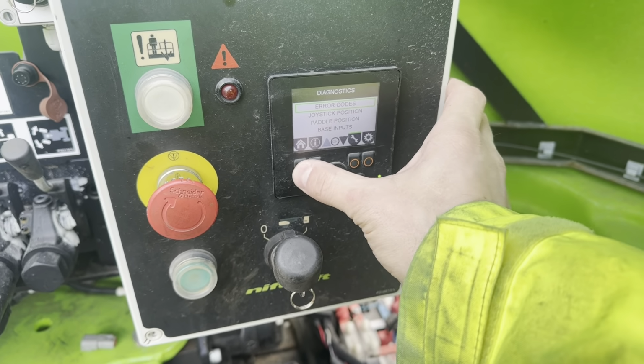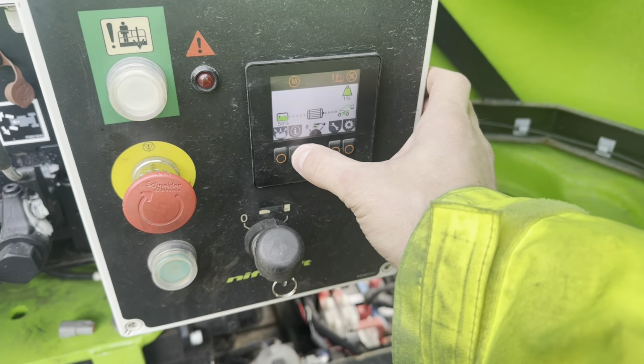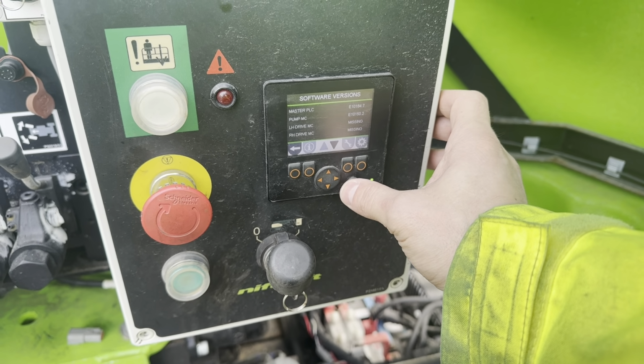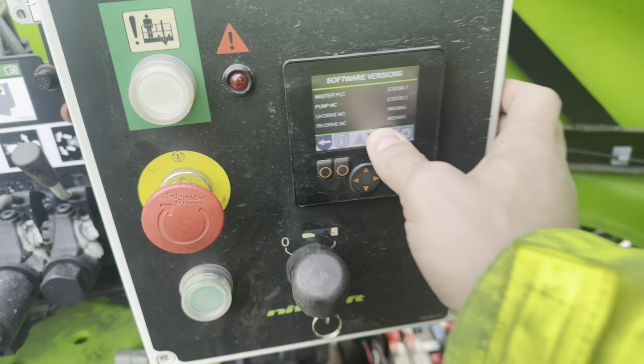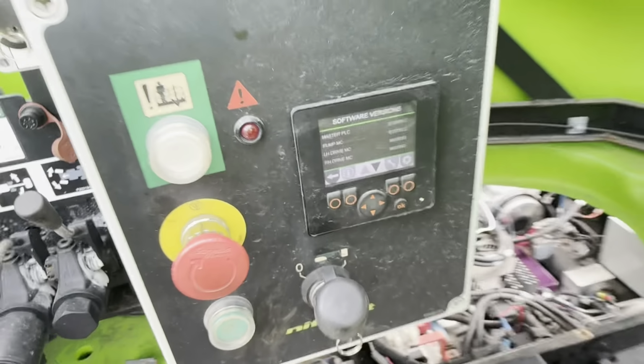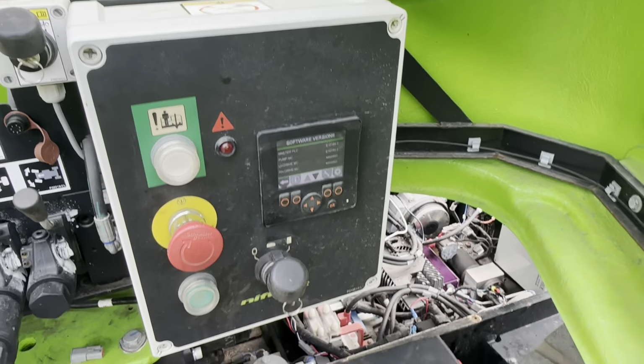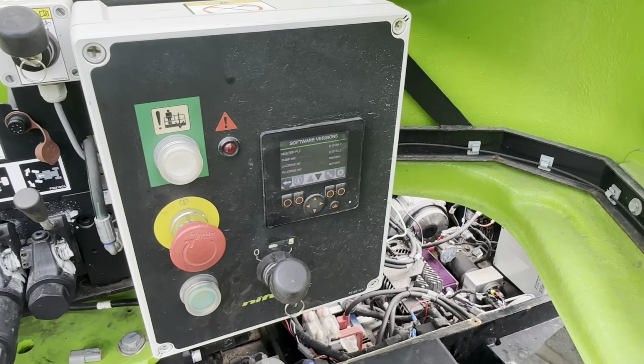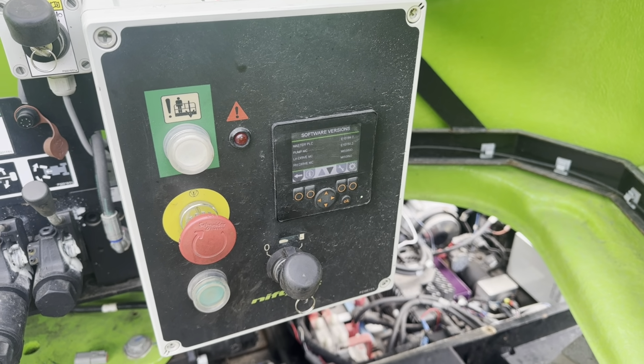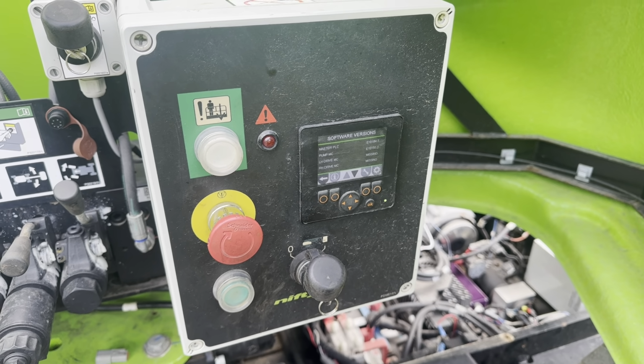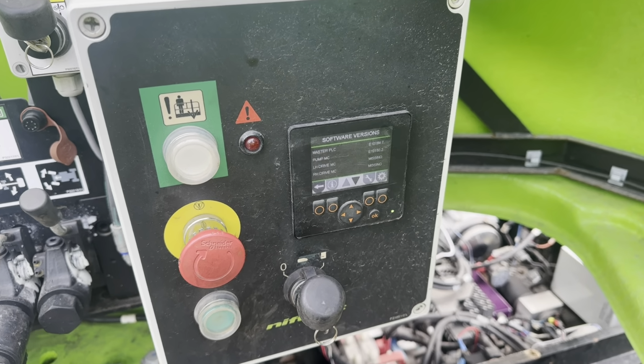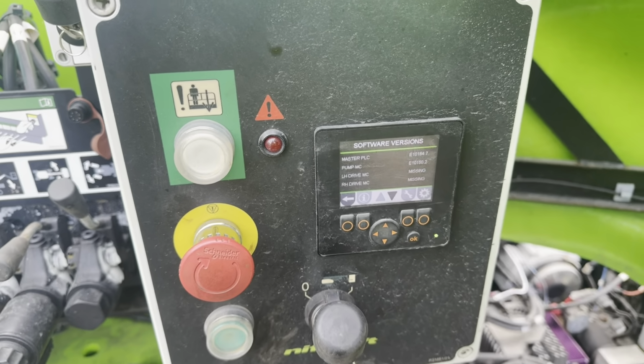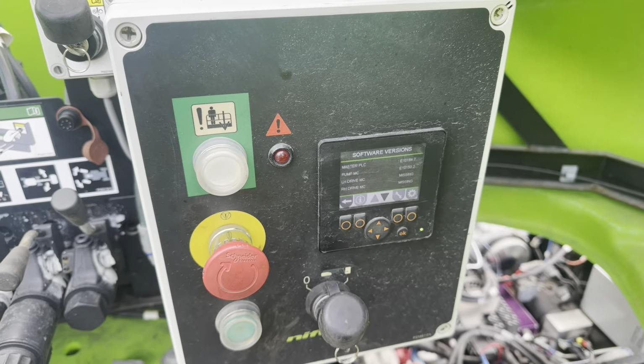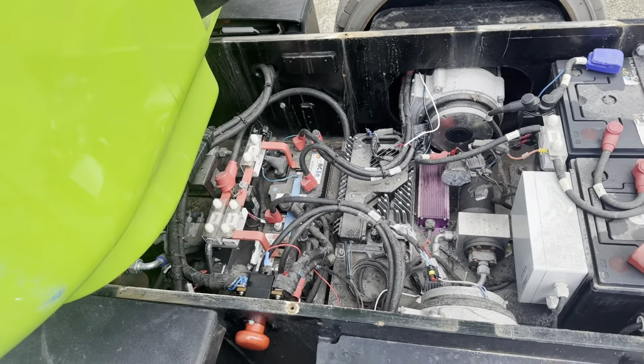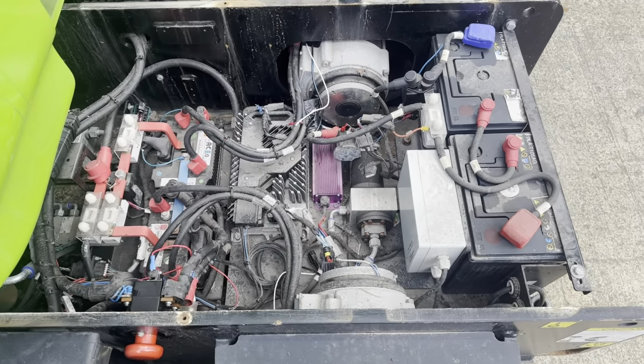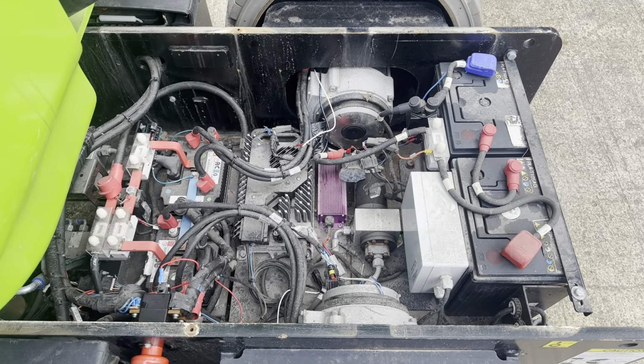If I look into the software, I have drive controllers missing. I don't know if that's right or wrong, but I would suspect the controller to start at least and give us an error saying the temperature sensor is open, but now it's completely dead. So it's interesting what's happening with this temperature sensor.